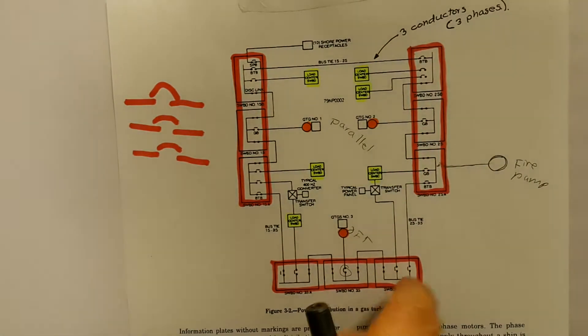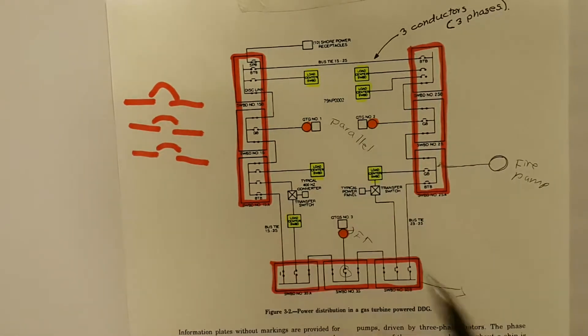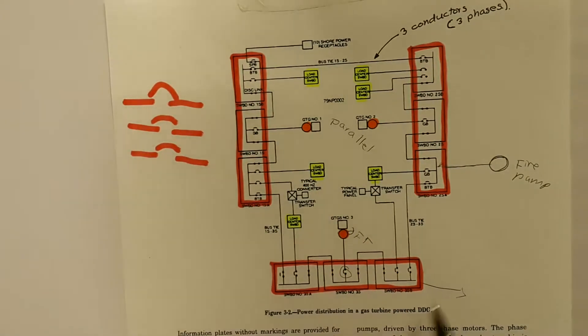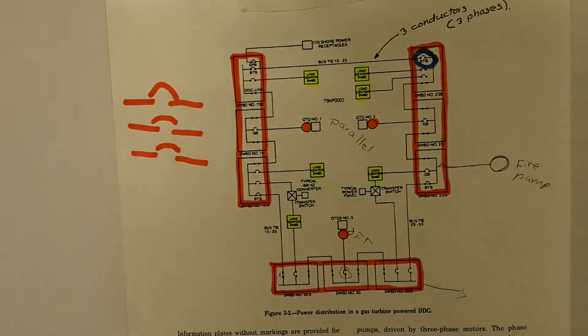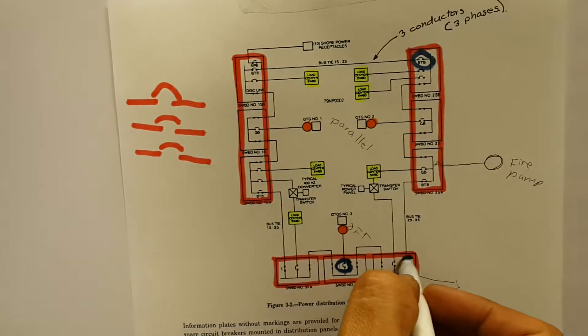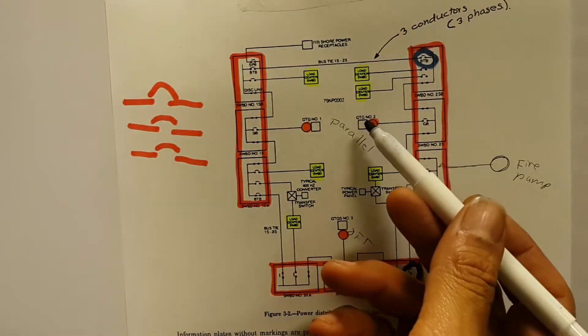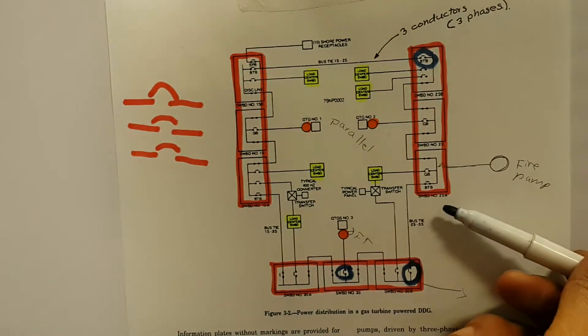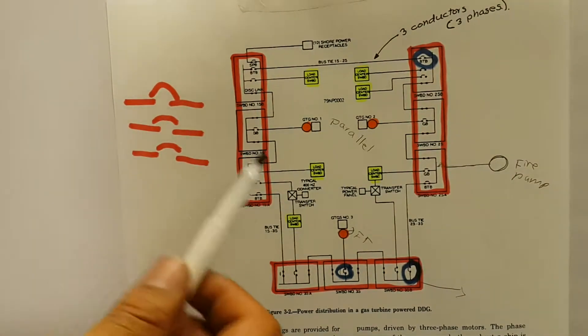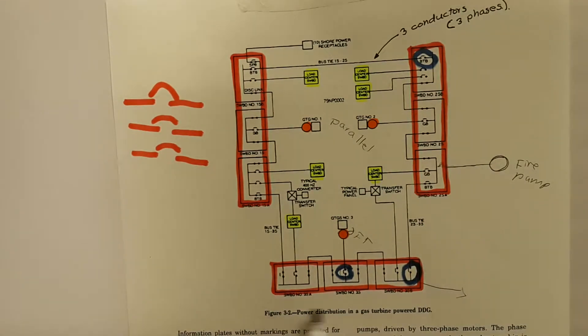So electrons going through some load connected to this one, some will be coming from number two generator, and some could be coming from number one generator. In that scenario, we could also split the bus. Remember this one is open, and we could open this generator breaker, this bus tie breaker over here. So now, number two generator will only be feeding number two switchboard loads, and number one generator will be feeding one switchboard and number three switchboard.